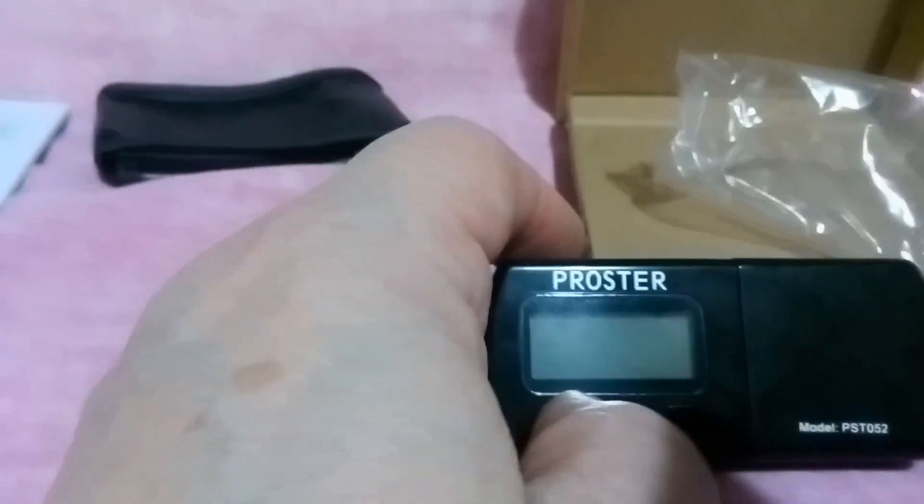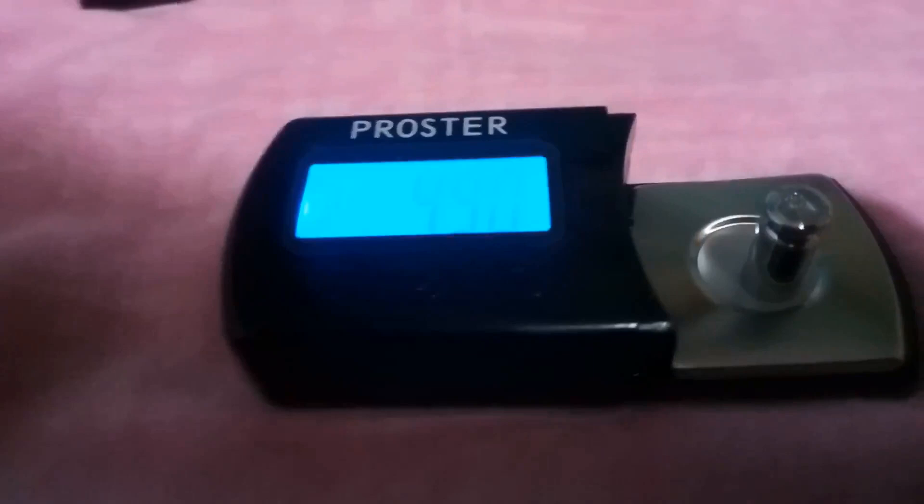It says eights on startup, then I put it on its back and now it says zeros — that's good. I put the calibration weight on — I believe that's a five gram weight — and after pressing tare it reads 4.9 grams. I'm on a slightly soft surface, so I think that's probably close enough. I'll accept 4.9.